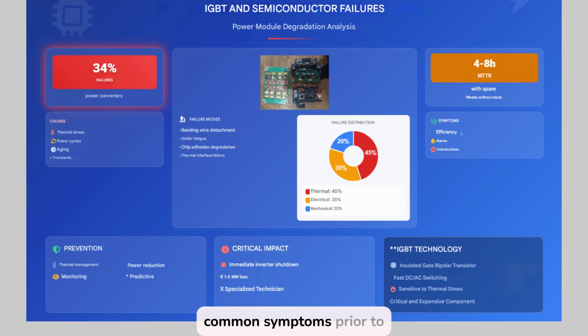The most common symptoms prior to or associated with the failure are progressive drop in inverter efficiency. SCADA alarms activated without apparent cause. Total shutdown of the inverter system with no remote restart option. Each failure of this type results in an immediate shutdown of the affected inverter. If there is no redundancy or auxiliary inverters, the loss of generation can range from 1 to 5 megawatts per event.